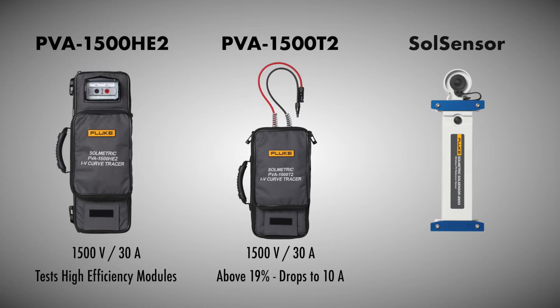They're both paired with the SolSensor, which measures the irradiance and temperature of the module so that we can convert the test data to standard test conditions and compare to manufacturer's data.